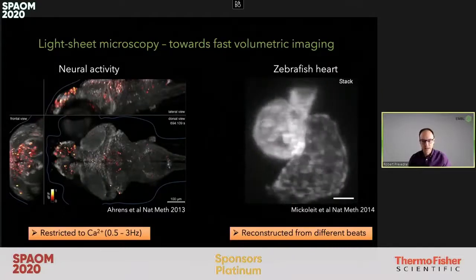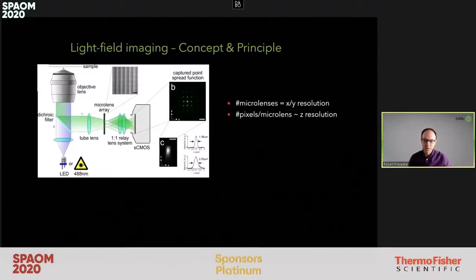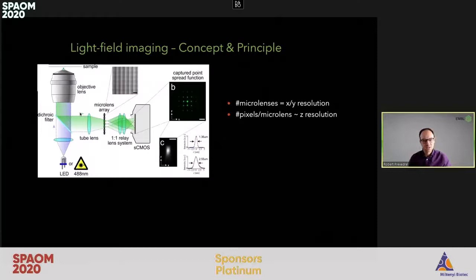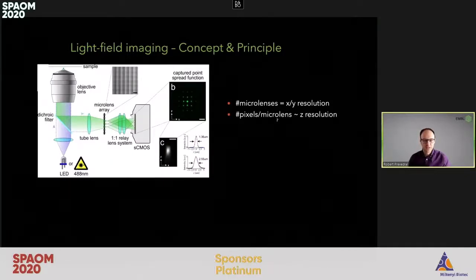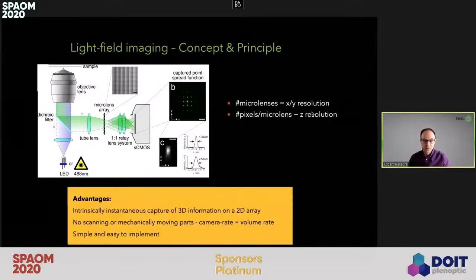This is exactly where light field microscopy can provide a fundamental advantage. In light field microscopy, we rely on measuring both the lateral and angular information of the light emitted by the sample. This can be achieved by introducing a microlens array into the imaging path of a conventional epifluorescence microscope. This microlens array gives access to both angular and depth information of the sample, where the number of microlenses translates to the lateral resolution, and the number of pixels behind one microlens defines the axial resolution.